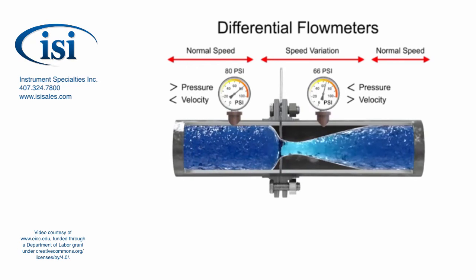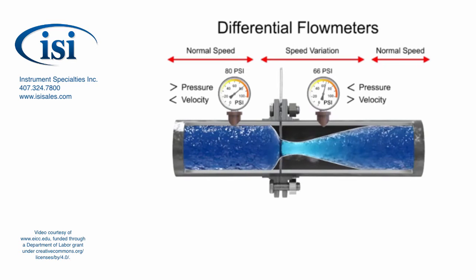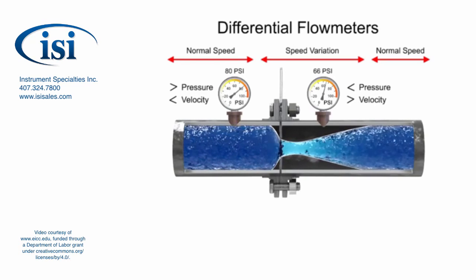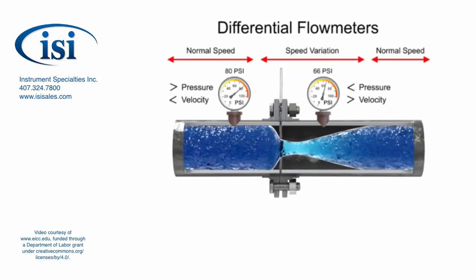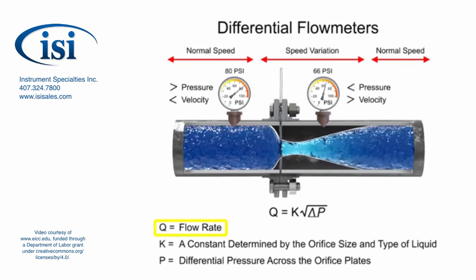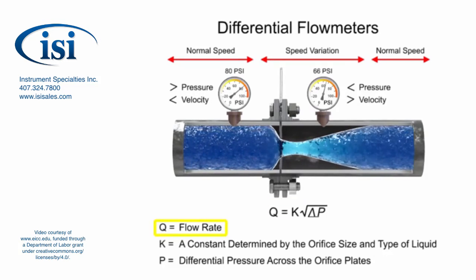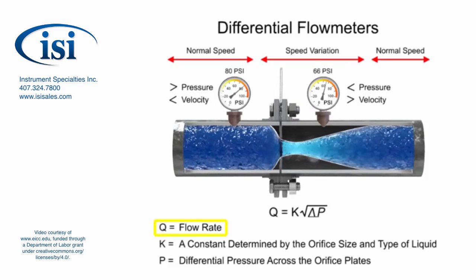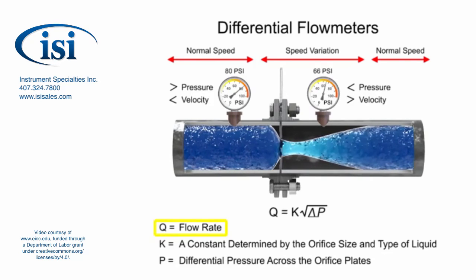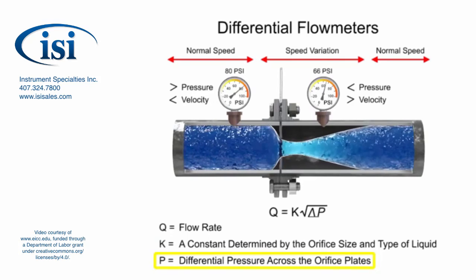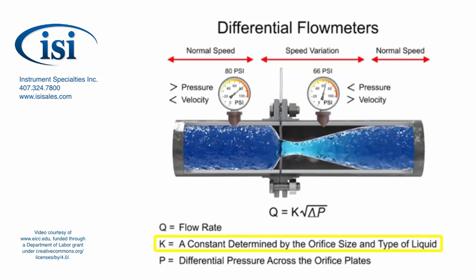With a known differential pressure and velocity of the fluid, the volumetric flow rate can be determined. The flow rate, q, of a fluid through an orifice plate increases in proportion to the square root of the pressure difference on each side multiplied by the k factor.